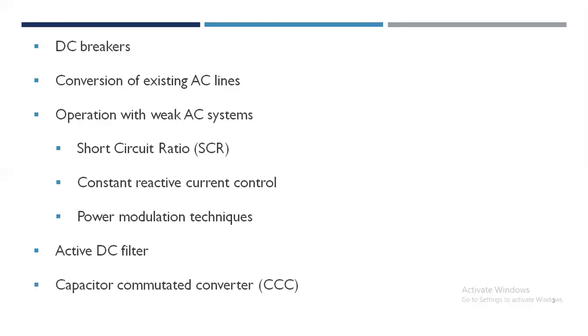Next is the capacitor commutated converter. This involves the connection of commutation capacitors in series with the valve side windings of the converter transformer. This is not strictly a new technology and it has been studied under the label of forced commutated converters. The advantages of the capacitor commutated converter, that is CCC, are improved voltage stability when operating with weak AC systems, reduced risk of commutation failures, and also less load rejection overvoltages and reactive power requirements.